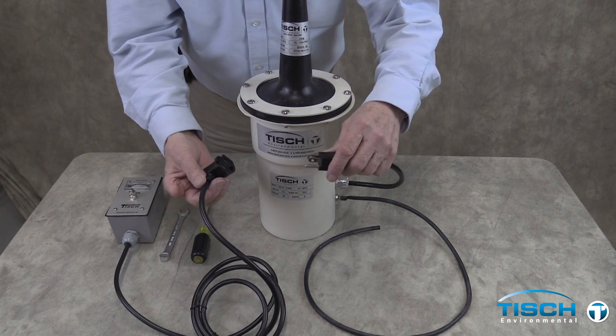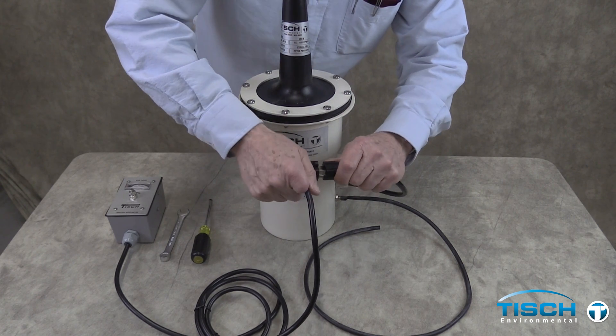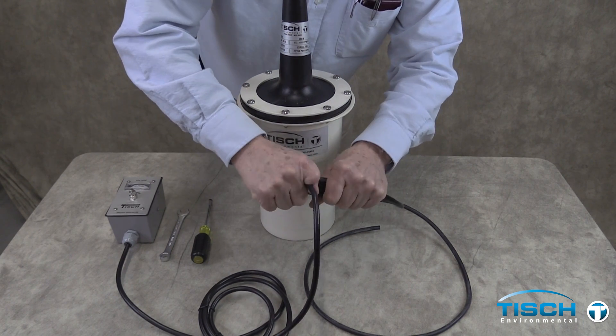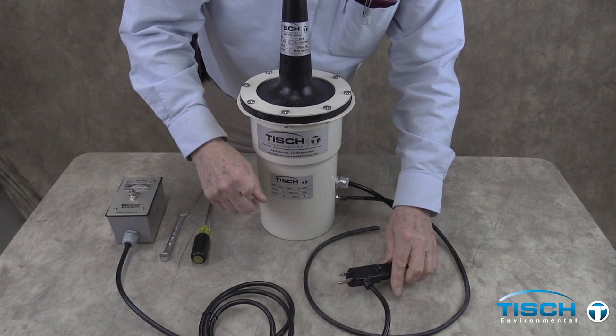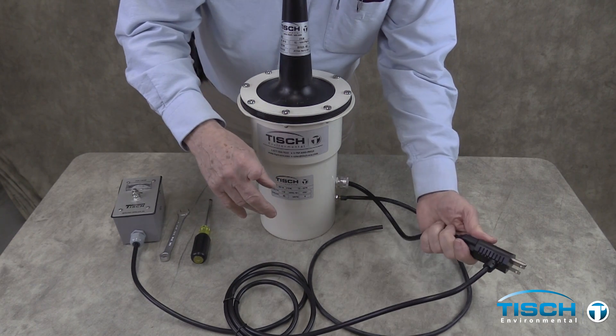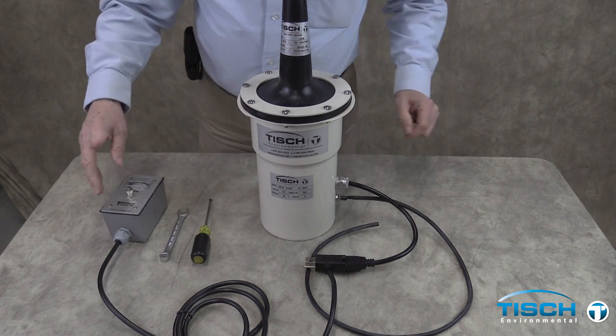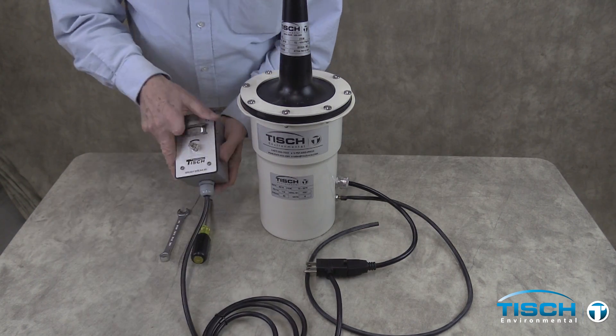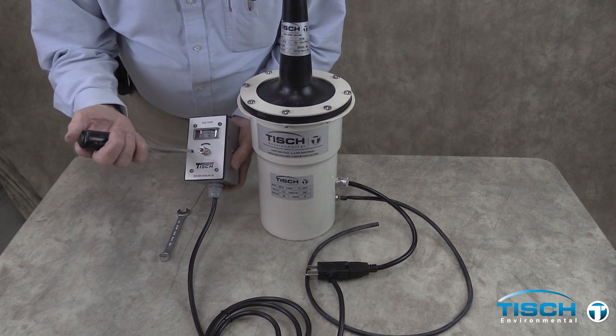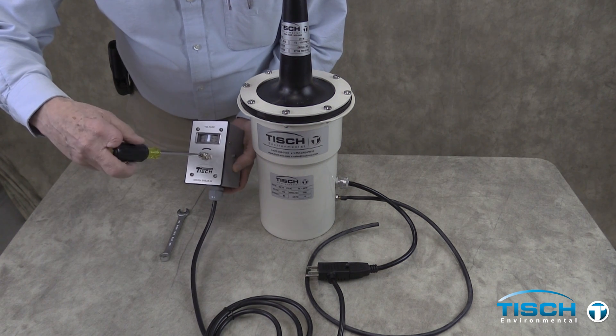Seat the new motor brushes using a TE-5075 brush break-in device at about 50 volts. This will enhance the life of the motor brushes. You can adjust the voltage of the brush break-in device using a flat head screwdriver and a 7/16 inch wrench.